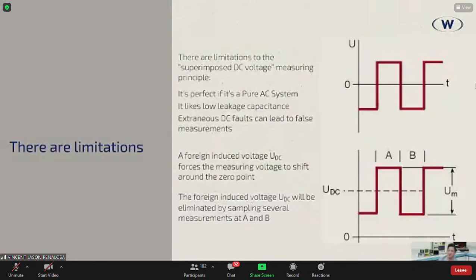Now, how do they compensate for this? No? Because superimposition of DC voltages, of course, has its limitations. Now, the limitations: it's great for pure sinusoidal AC, which is next to impossible nowadays. Now, if there is an induced DC leakage current there, DC voltage induced into the AC circuit, this kind of forces the measuring voltage to shift around the 0 point. Now, when you think about this, you have that pump. It actually studies that, shifts that accordingly, and it acts kind of like some sort of an active filter where it tries to cancel out that capacitance. Why? For it to be able to measure properly.